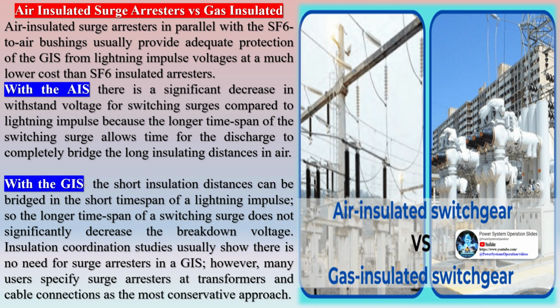Air-insulated surge arresters in parallel with the SF6-to-air bushings usually provide adequate protection of the GIS from lightning impulse voltages at a much lower cost than SF6 insulated arresters.